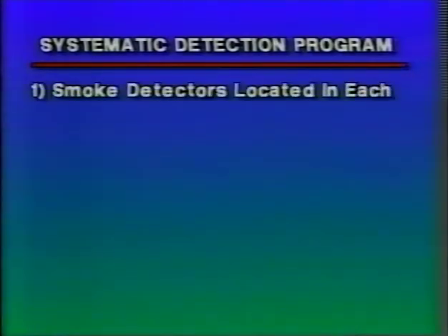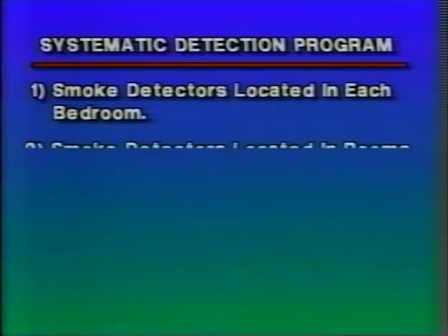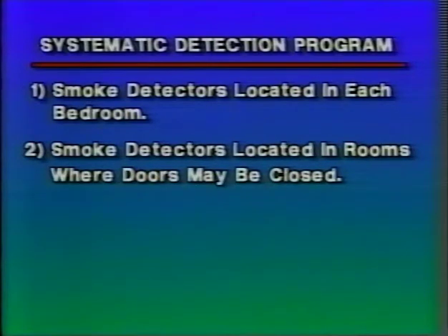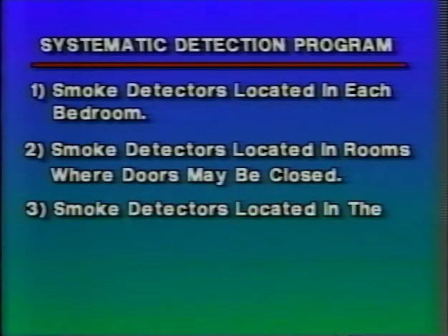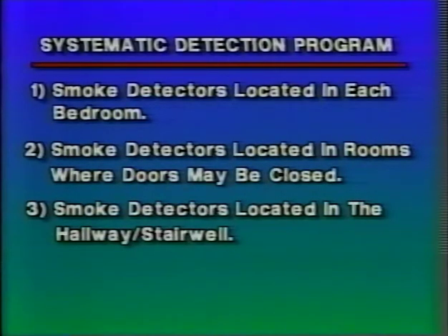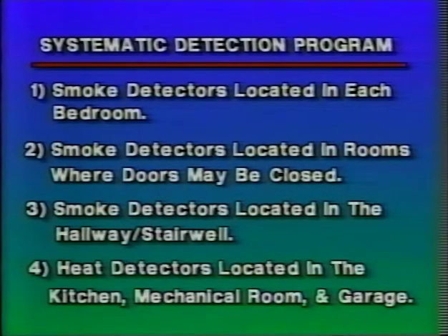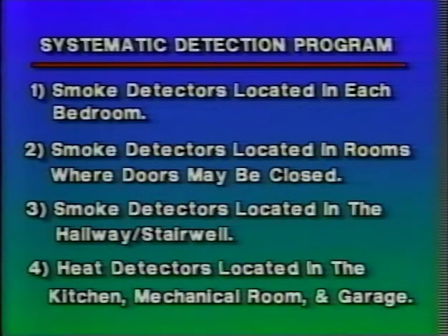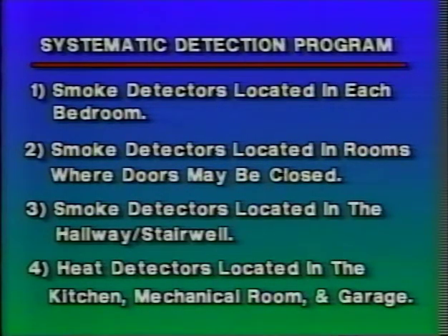Based on the data obtained from 16 fire tests, the following conclusions were developed. A systematic approach to residential fire protection should be utilized. A systematic detection program should consist of the following: smoke detectors located in each bedroom, smoke detectors located in rooms where doors may be closed, smoke detectors in the hall or stairwell, heat detectors located in areas where smoke detectors will give a false alarm. These include the kitchen, the mechanical room, and garage.